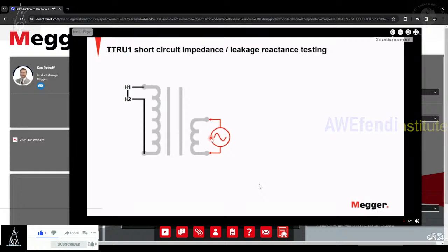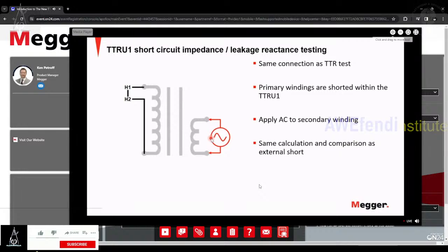And that is where with the TTRU1, using the same connection that you use for turns ratio, we use internal shorting and lead compensation within the TTRU1 to give you that accurate turns ratio measurement. It's going to be the same connection as a TTR test, as I mentioned a couple times now. We're going to short that primary winding within the instrument, apply the AC to the secondary, and then we use that same calculation and comparison as the external short, doing it in the step-down method. But with that internal shorting, with that lead compensation, we're going to get you that reliability that you require, that repeatability to be able to go out and make the best informed decisions about your asset.